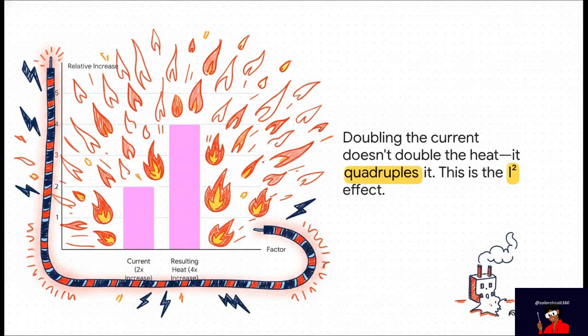If you just double the amount of current running through a wire, you don't get double the heat, you get 4 times the heat. A small, innocent little increase in power use can lead to a huge, potentially dangerous spike in temperature. This is exactly why undersized wiring is such a common failure point.